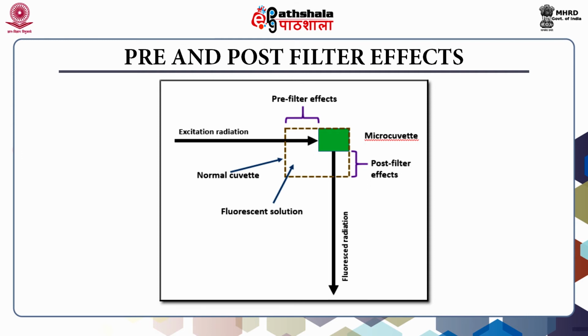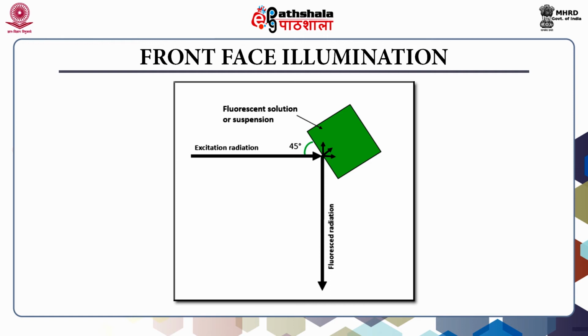The use of microcuvettes alleviates these effects to some extent. Front face illumination setup removes pre and post filter effects. In front face illumination, a cuvette with one optical face is used and the excitation and the emission occur at the same face. This setup is less sensitive than the 90-degree illumination setup.